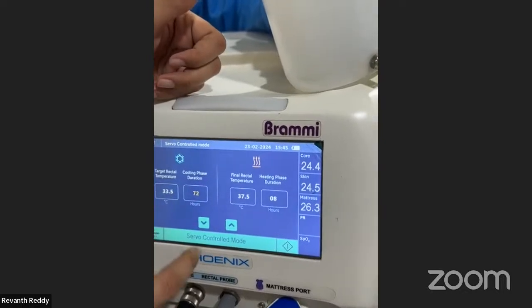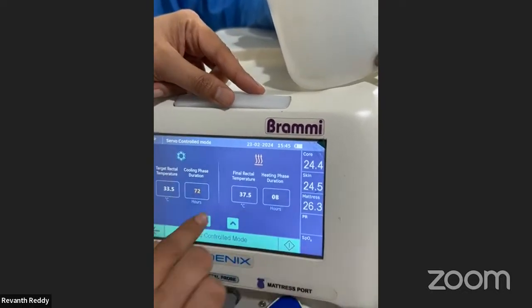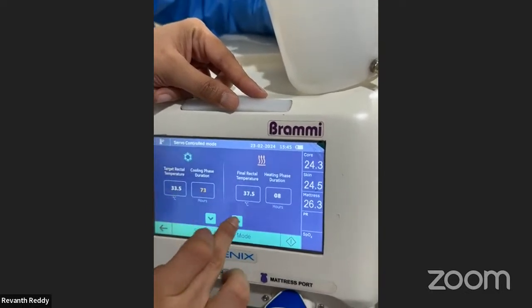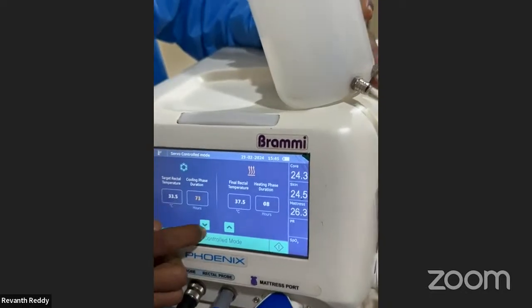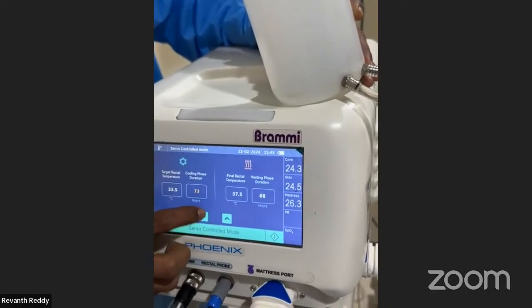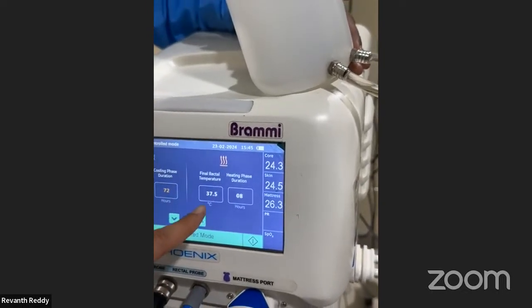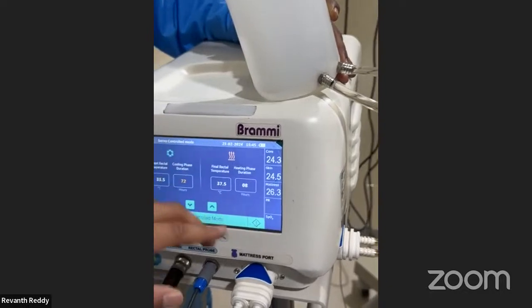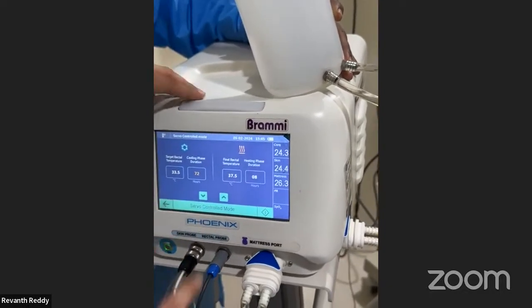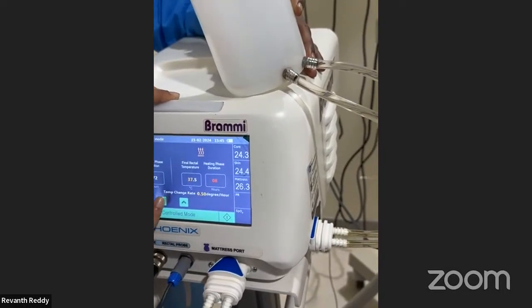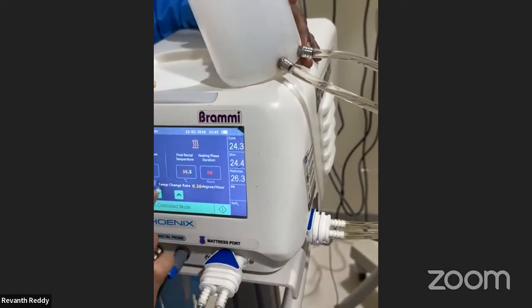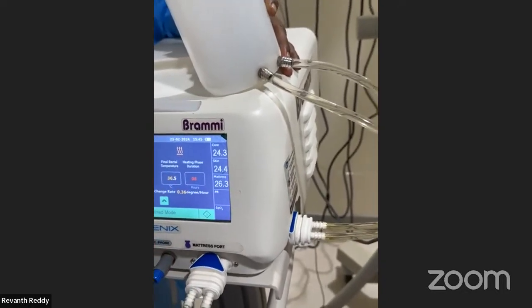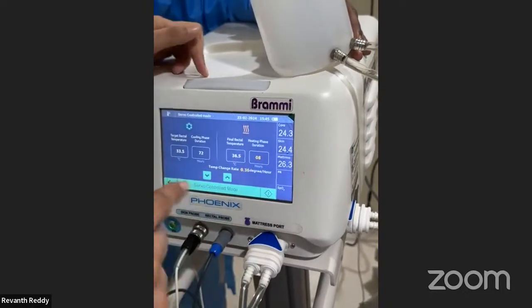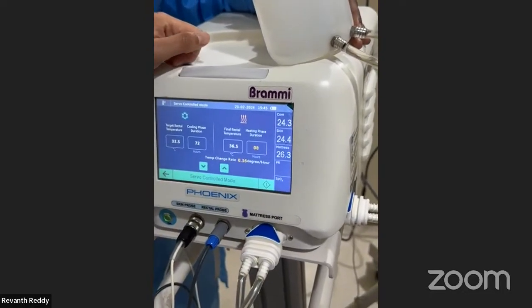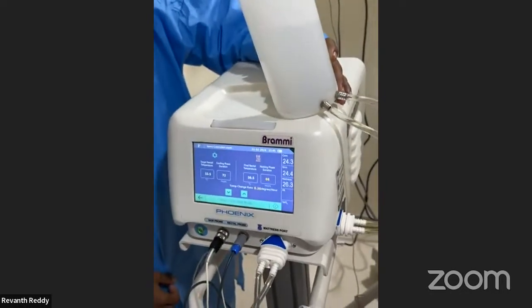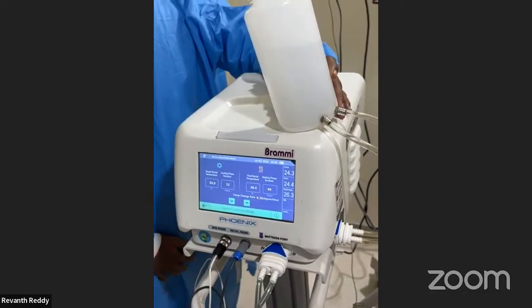Duration of cooling, generally we all take 72 hours, but you have the option of either decreasing or increasing it. So this usually is to be set at 72 hours. Then the final rectal temperature, which is the temperature that we desire after we finish cooling phase, this can be chosen. So supposing you want to keep it at 36.5 degrees Celsius. Now it's okay, so we have chosen 36.5 degrees, and then you can also choose the duration of hours over which you want to do the rewarming. So supposing you want to choose the range of rewarming can range from 0.2 to 0.5 degrees Celsius per hour.